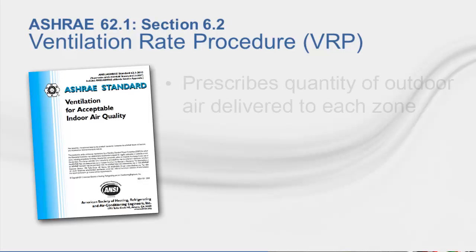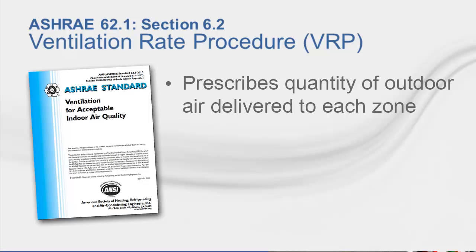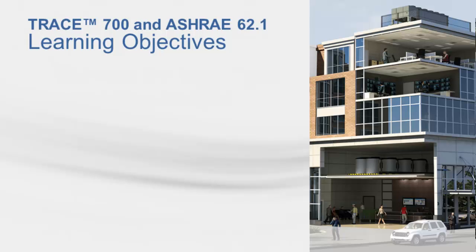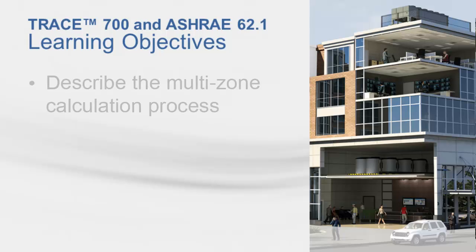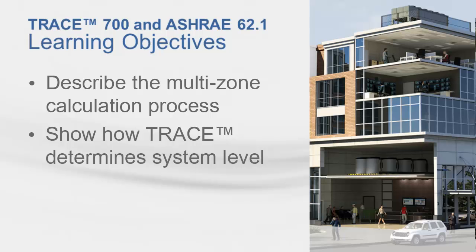Specifically, I'm going to be talking about the ventilation rate procedure, which is covered in Section 6.2 of ASHRAE Standard 62.1. The standard prescribes the quantity of outdoor air that must be delivered to each zone based on the expected use of that zone, and then prescribes how to calculate the outdoor air flow needed at the system level intake. In today's video, I will show you the process for calculating the outdoor air flow for a multi-zone system, walk you through a hand calculation, and show how TRACE determines zone level and system level outdoor air fractions.